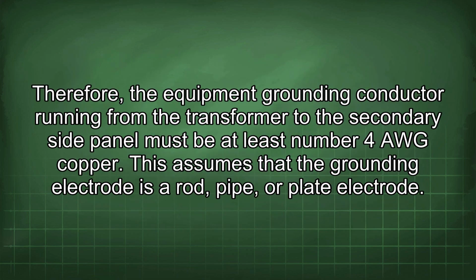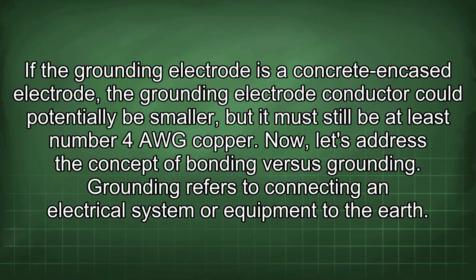Therefore, the equipment grounding conductor running from the transformer to the secondary side panel must be at least number 4 AWG copper. This assumes that the grounding electrode is a rod, pipe, or plate electrode. If the grounding electrode is a concrete encased electrode, the grounding electrode conductor could potentially be smaller, but it must still be at least number 4 AWG copper.